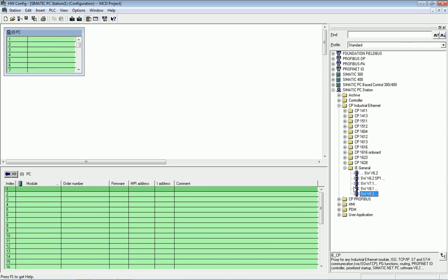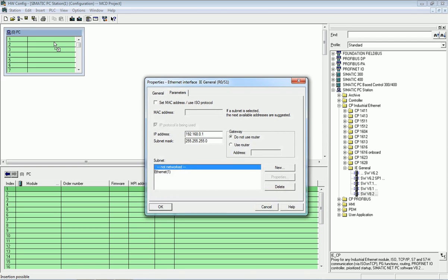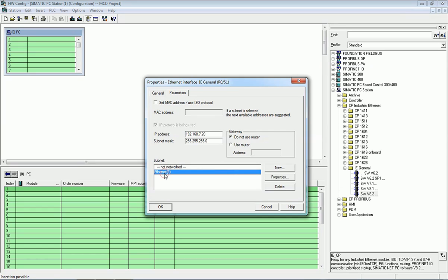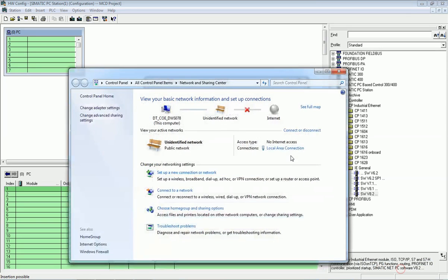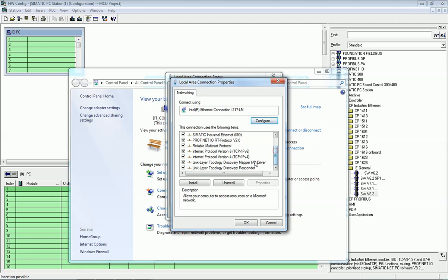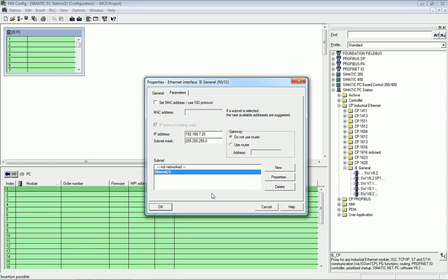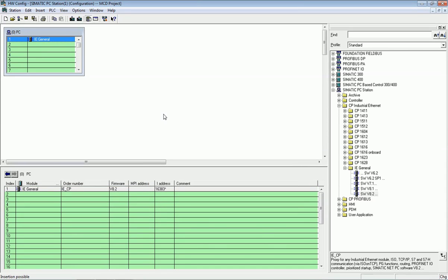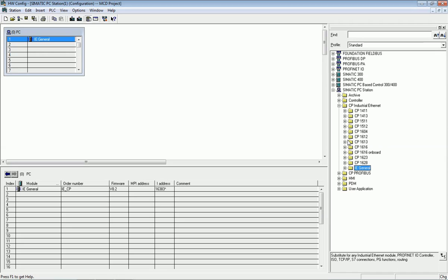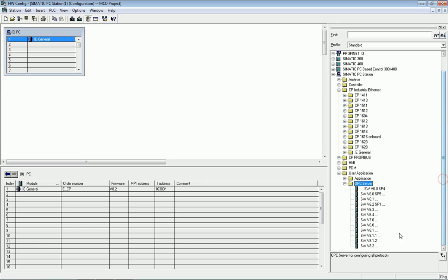We select the latest version and drag and drop it. The screen asks for an IP address. We will keep the same IP address as the system. First, we select the same subnet as the PLC, then we set the IP address. The system IP address is 7.20, and we will keep the same IP address for the Industrial Ethernet here. The subnet is also the same Ethernet subnet — press OK.